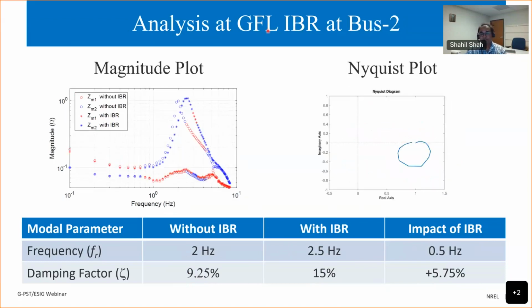We do that with another plant which is grid following, and we find that because this Nyquist plot is not encircling the origin, the damping without this IBR is positive. So removing this grid following inverter is not making the system unstable, but it is still reducing the damping that we can get from the modal impedance plots. It is increasing the resonance frequency from 2 hertz to 2.5 hertz, which is what we see with the full system, and it is adding damping by 5.75%.